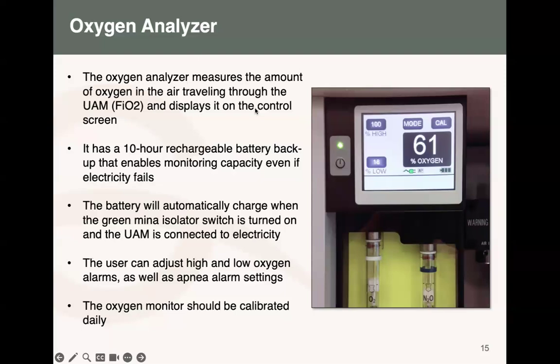The oxygen fraction shows how much you are giving. But it also has an alarm where you can set the high and the lower limit, and it will alarm when you go beyond the limit. It should be calibrated basically on a daily basis. If you have 100% oxygen, yes, you can calibrate the air and oxygen. But if you don't have 100% oxygen, we advise you to calibrate with only air, as you will see later. Next.